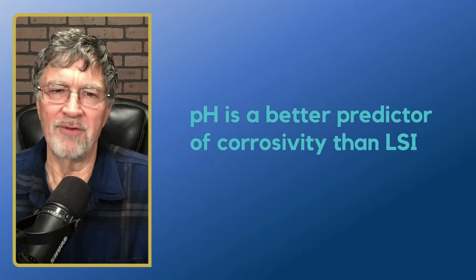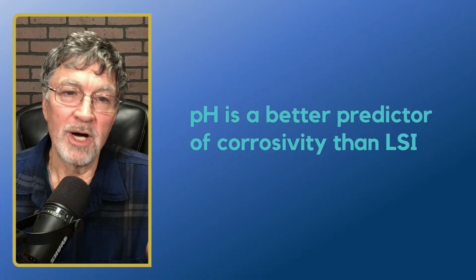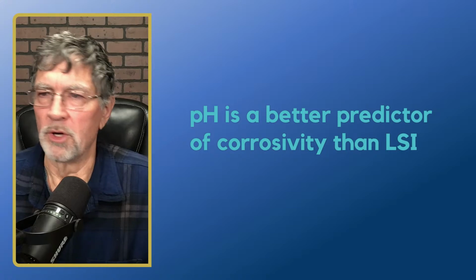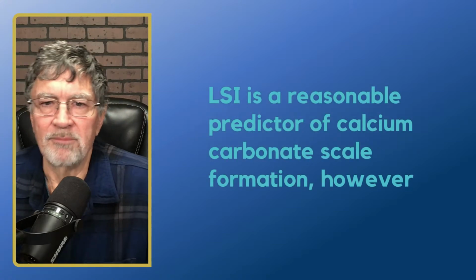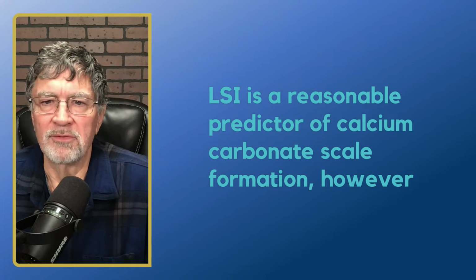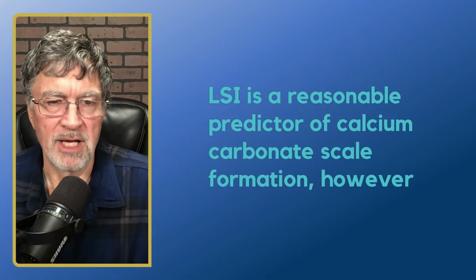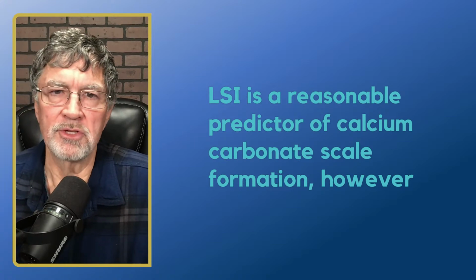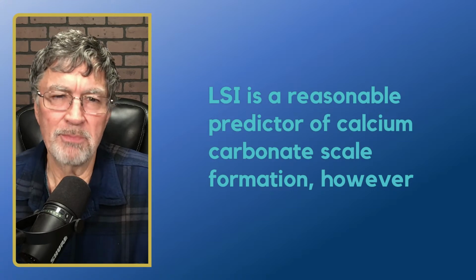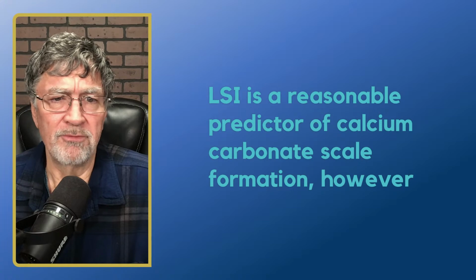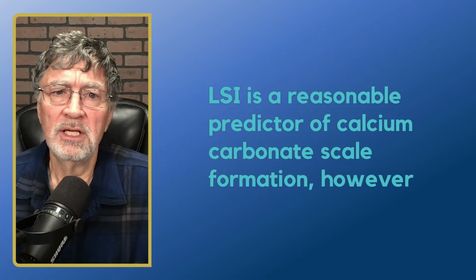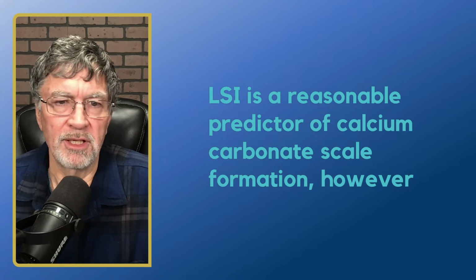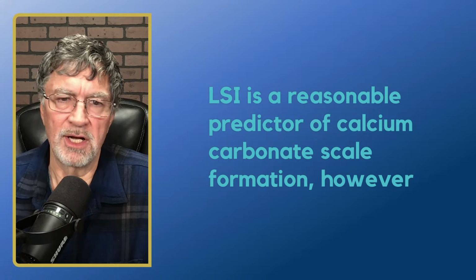So all these tools that we have, all these measurements we do, we want to do a number of them and look at them in total to really confirm what our conclusions are. All right, LSI is a reasonable predictor of calcium carbonate scale formation, however. It does tell you if you're oversaturated with regard to calcium carbonate, and is a pretty good predictor of the potential for forming calcium carbonate scale in your well and the plugging. But once again, it will not predict iron oxides, manganese oxides, those types of things.